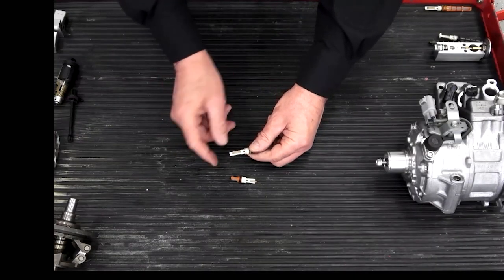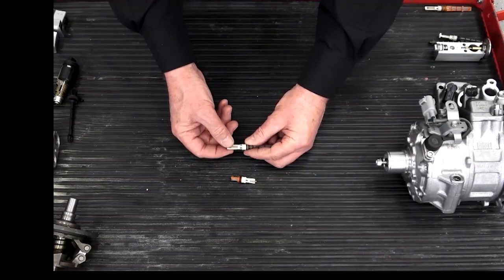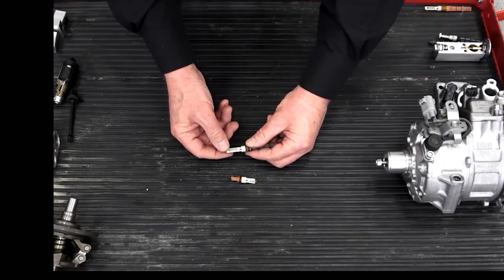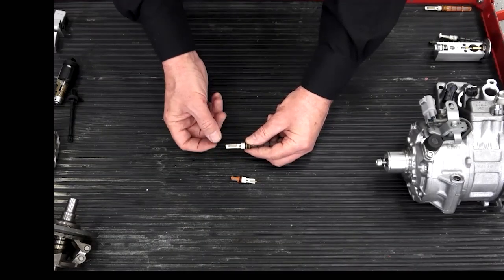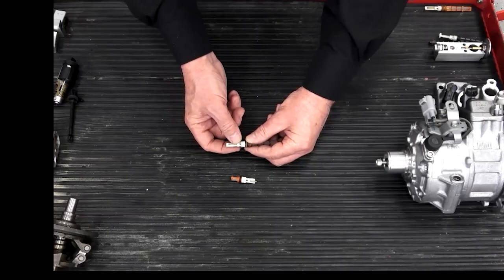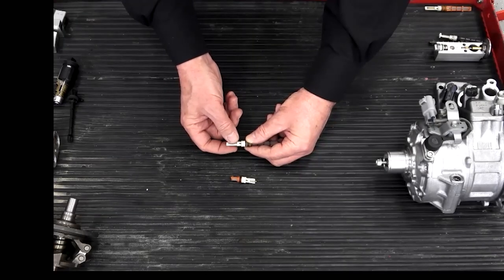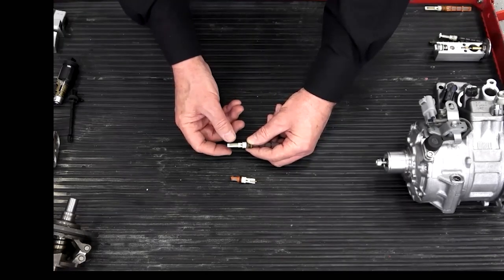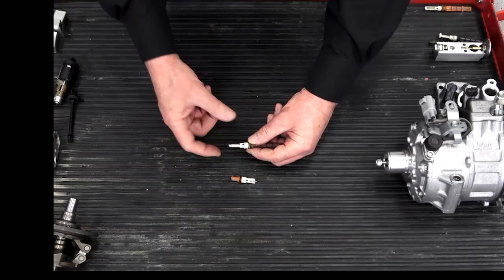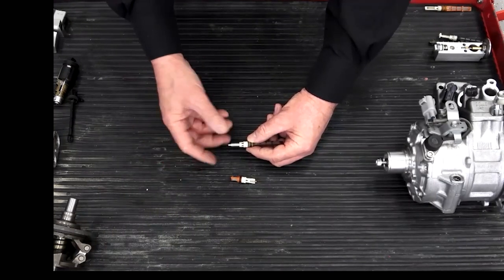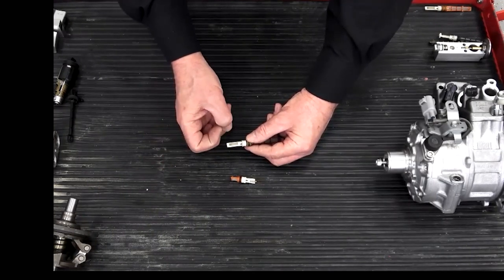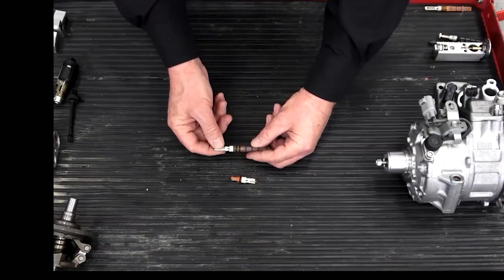This piece on the other side that looks like a filter is actually a diffuser. It breaks up the liquid refrigerant as it enters the evaporator, so you get better boiling and evaporation. The refrigerant boils more easily if I break up the liquid flow as it enters the evaporator.